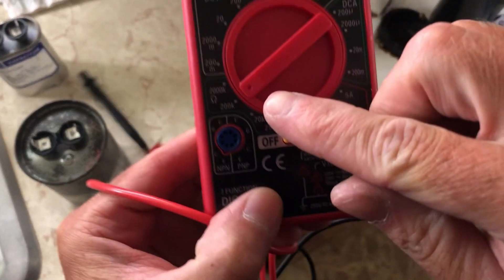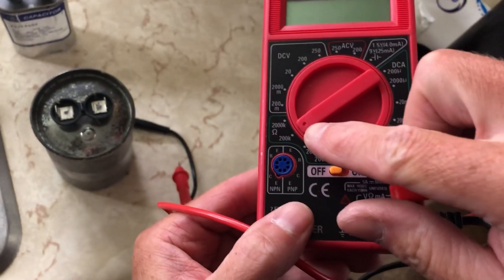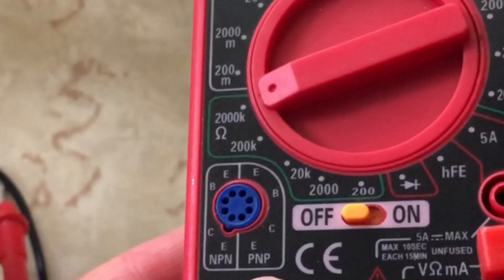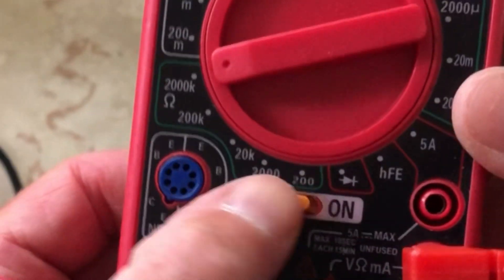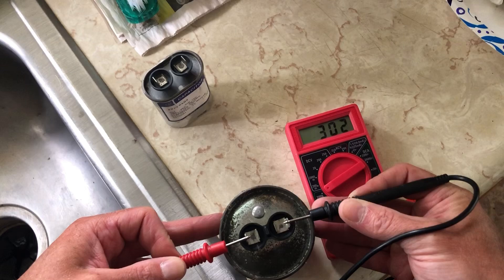This is just a $7 multimeter I got from Harbor Freight. You want to go to the ohms side on the highest setting — here we'll turn it to 2,000k ohms — and turn the multimeter to the on position. Go ahead and take your black or negative lead, touch that first, and then the red or hot lead, touch it second to the connection points on the capacitor.